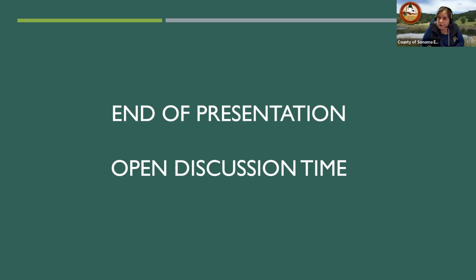So there are a couple of questions related to this, so I'll just combine them. Can a heat pump be used to replace a gas furnace in a hydronic heating system? Yes. I mean, you can heat. So there are heat pump water heaters. A hydronic system uses hot water to heat the space. And so you can have a heat pump water heater that provides hot water to a fan coil and blows air across a coil. You can use a heat pump water heater to heat radiant floors.